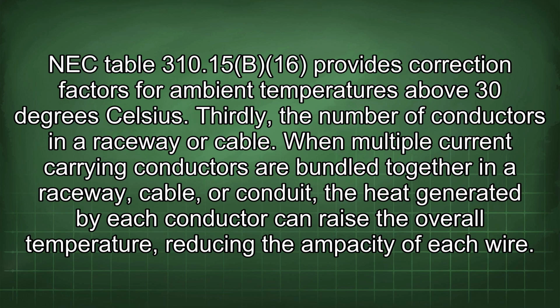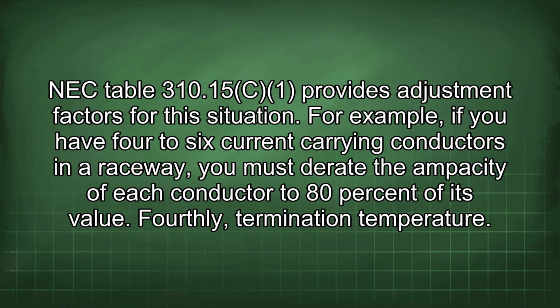Thirdly, the number of conductors in a raceway or cable. When multiple current-carrying conductors are bundled together in a raceway, cable, or conduit, the heat generated by each conductor can raise the overall temperature, reducing the ampacity of each wire. NEC Table 310.15(C)(1) provides adjustment factors for this situation. For example, if you have 4 to 6 current-carrying conductors in a raceway, you must derate the ampacity of each conductor to 80% of its value.